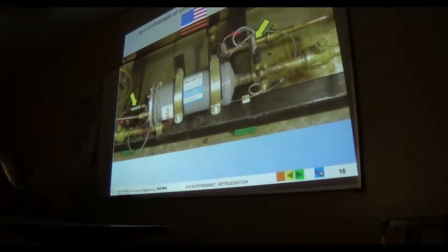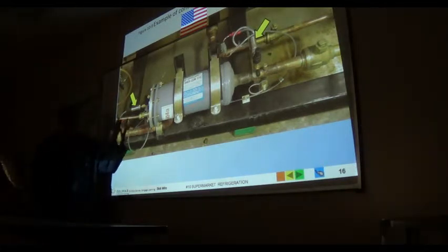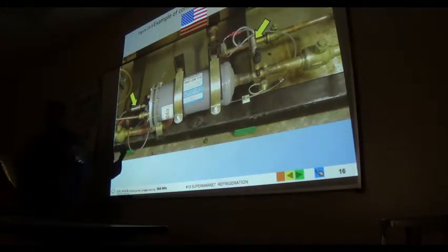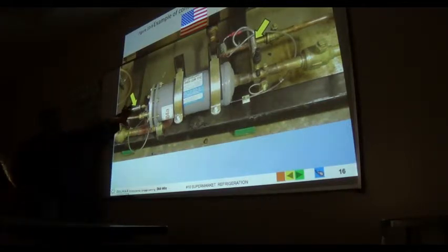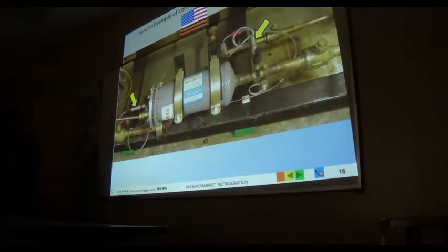And typically they will tell you that you can take it in a glass with ice at 32 degrees and then check the resistance, which should be about 30 ohms for NTC. And PTC, it may be like 300 up to 1,000. So they will give you all the test values from there. But every one of these is kind of proprietary, manufacturer specific. There's nothing generic about these, so you can't go and buy one that was made by his company and put it in a piece of equipment that was made by his company.